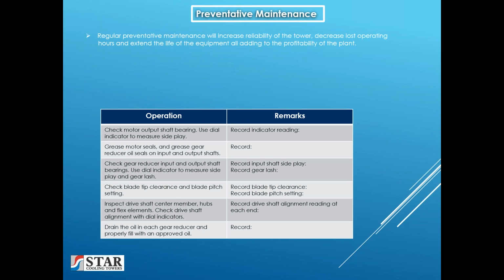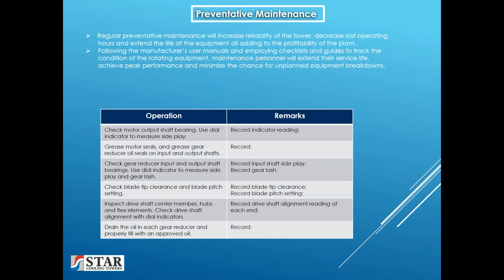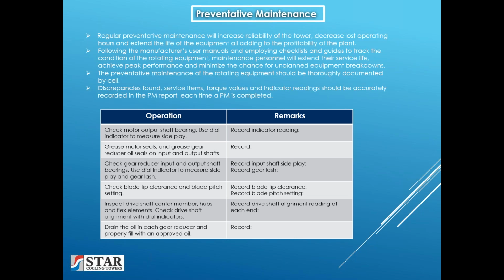Regular preventative maintenance will increase reliability of the tower, decrease lost operating hours, and extend the life of the equipment, all adding to the profitability of the plant. By following the manufacturer's user manuals and employing checklists and guides to track the condition of the rotating equipment, maintenance personnel will extend their service life, achieve peak performance, and minimize the chance for unplanned equipment breakdowns. The preventative maintenance of the rotating equipment should be thoroughly documented by cell. Discrepancies found, service items, torque values, and indicator readings should be accurately recorded in the PM report each time a PM is completed.